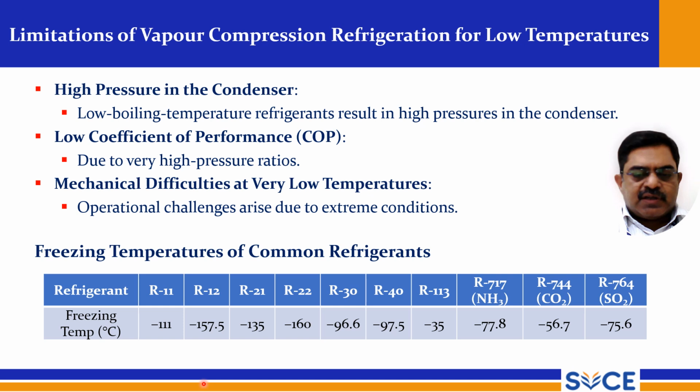For each refrigerant there are freezing temperatures. For R11 it is minus 111 degrees Celsius. For R12 it is minus 157.5 degrees Celsius. For R21 it is minus 135 degrees Celsius. For R22 it is minus 160 degrees Celsius. For R40 it is minus 97.5 degrees Celsius.